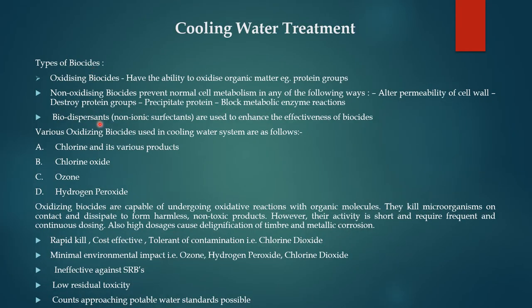Types of biocides: Oxidizing biocides have the ability to oxidize organic matter or protein groups. Non-oxidizing biocides prevent normal cell metabolism in any of the following ways: alter permeability of cell wall, destroy protein groups, block respiratory protein, and block metabolic enzyme reactions. Biodispersants, which are non-ionic surfactants, are used to enhance the effectiveness of biocides.